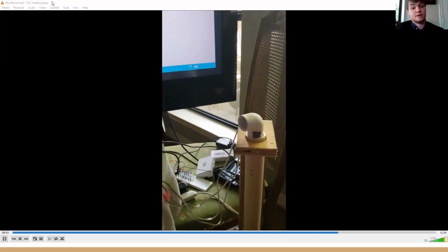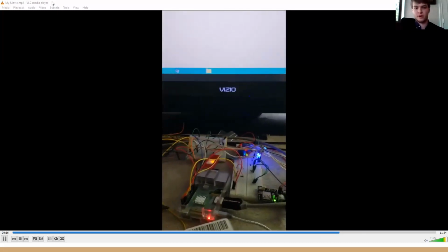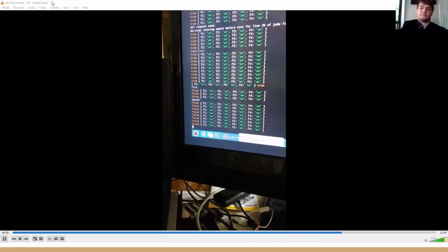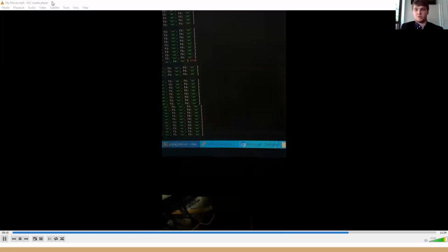So it should be, I believe it's on F2. No, it's on F4. We had raised it all the way up to F4. So I'm going to show, yeah, they're all on. So it's on F4, and I'm going to show that using the magnet, it'll come back down and turn off all those flags as the water lowers. And then when it reaches F2, it'll turn off the pump. That's the way it's coded.